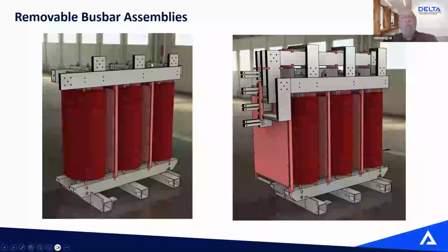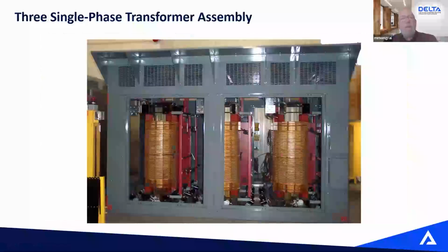So to remove that low voltage busing, mainly you're going to have to undo six mechanical joints, the mechanical joints that attach it to the top of the core and coil, and then you will have your electrical joints from phase A, B, C, and neutral. So usually it's going to be a NEMA 4 connection. So 20 electrical joints, six mechanical joints, and you can lift the entire low voltage bus rack and take it off so that we can have something that will run through that smallest opening, if I could say.